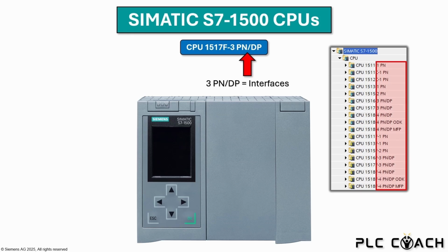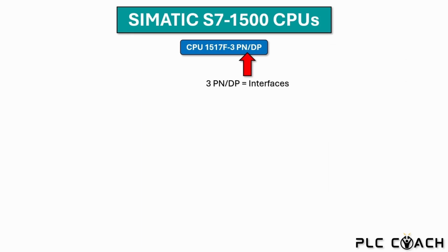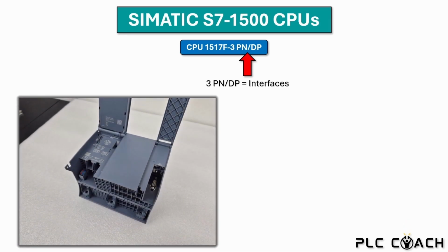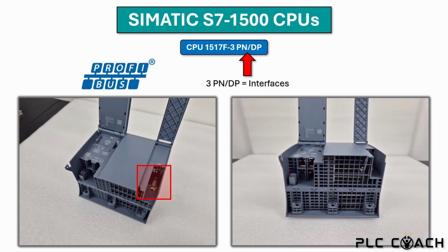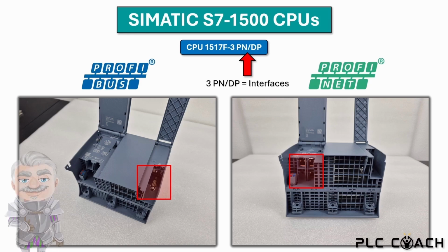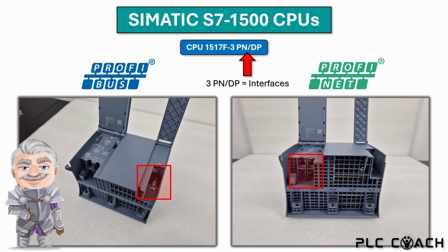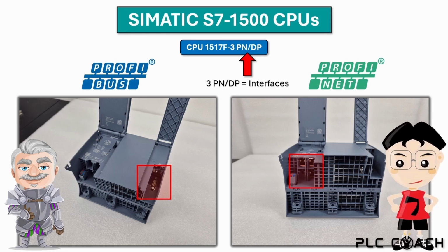What I mean can be easily seen when you open the covers of the CPU. Here you can see the DP interface, which is for Profibus. On the left side, you will see 3 LAN ports. These can be used for Profinet. Profibus and Profinet can be used to exchange information with other devices. However, Profibus is considered to be outdated. Profinet is now the new standard. But there is still a controller with a Profibus port available.